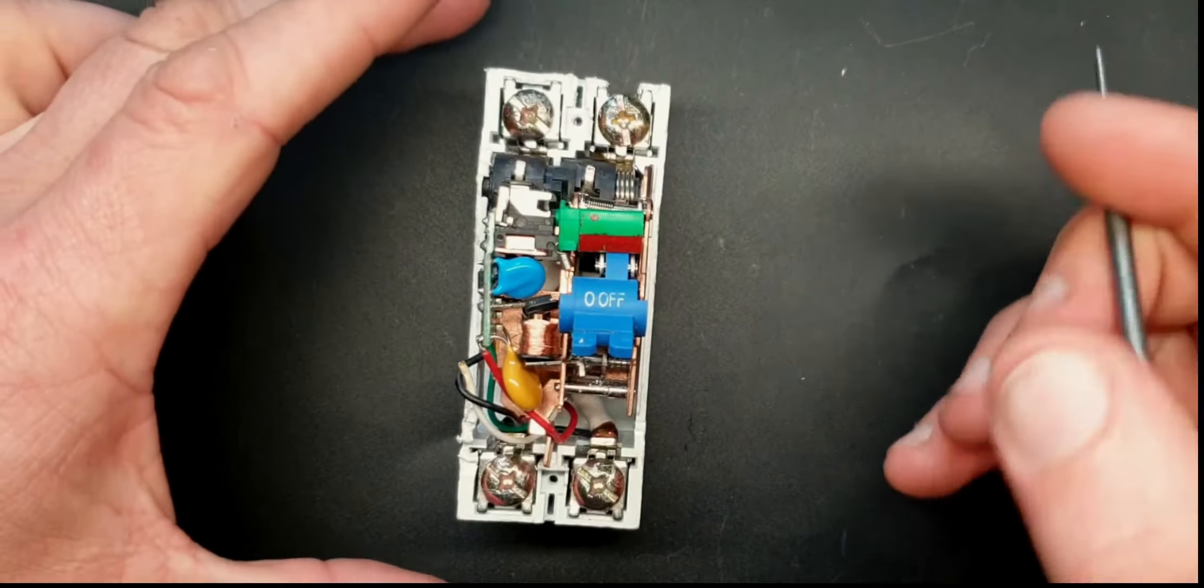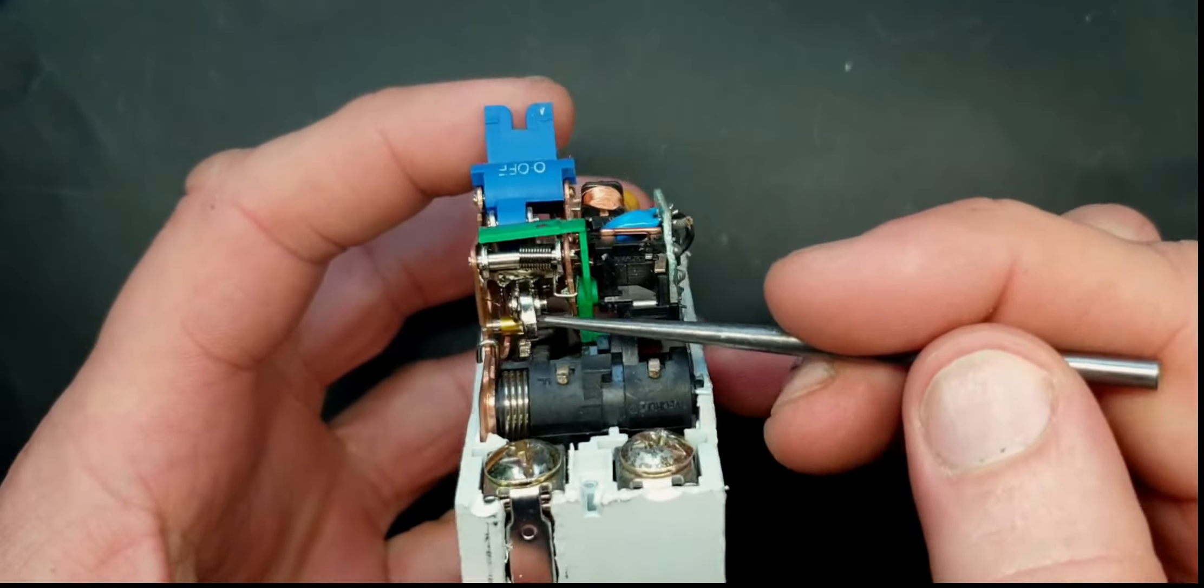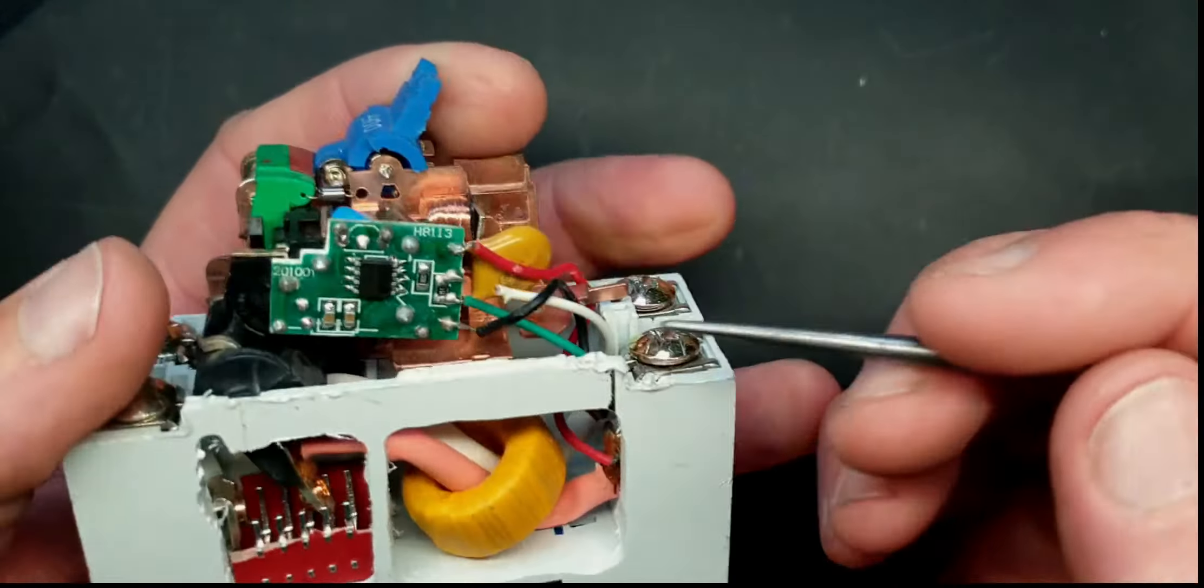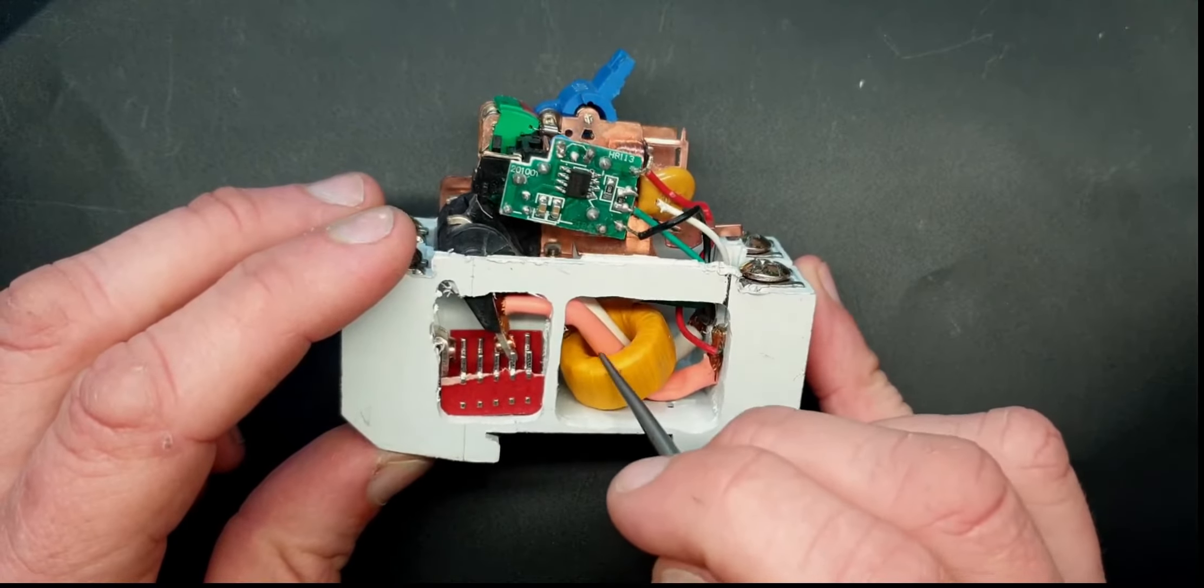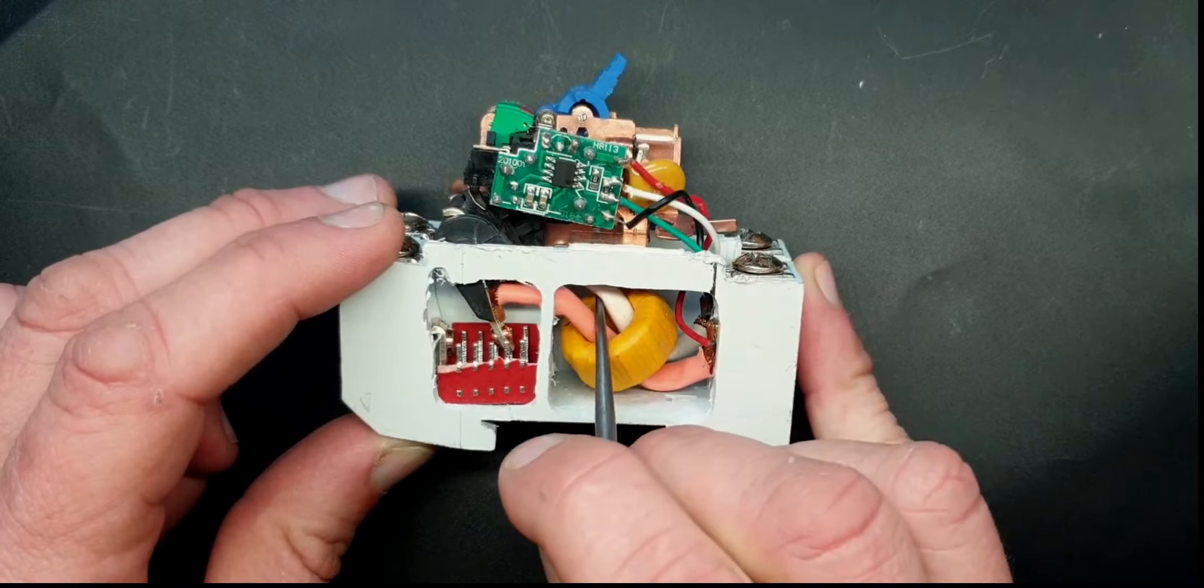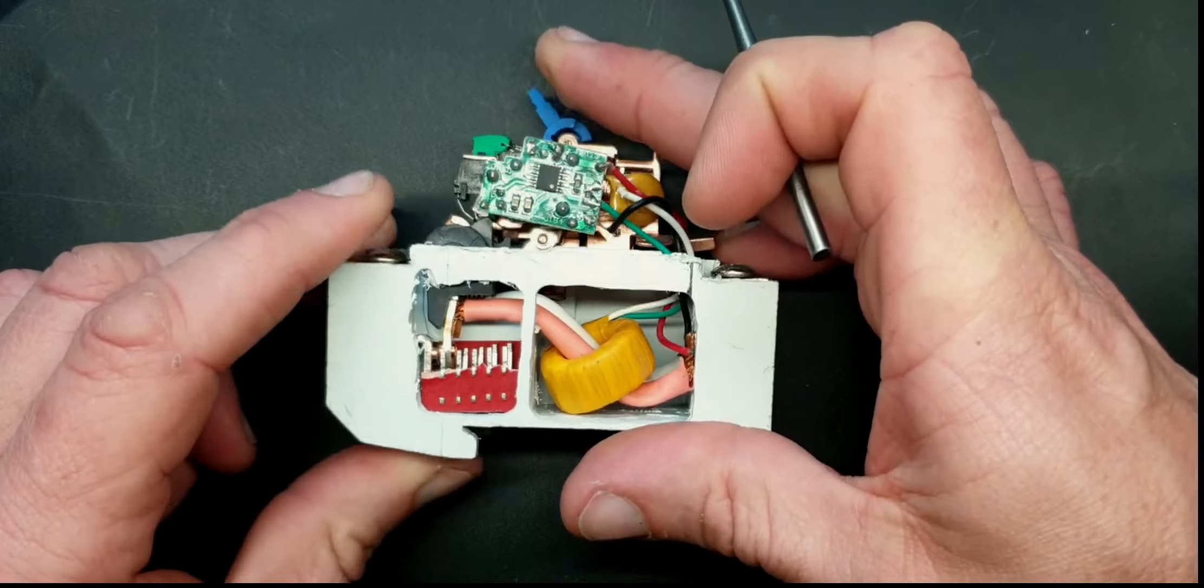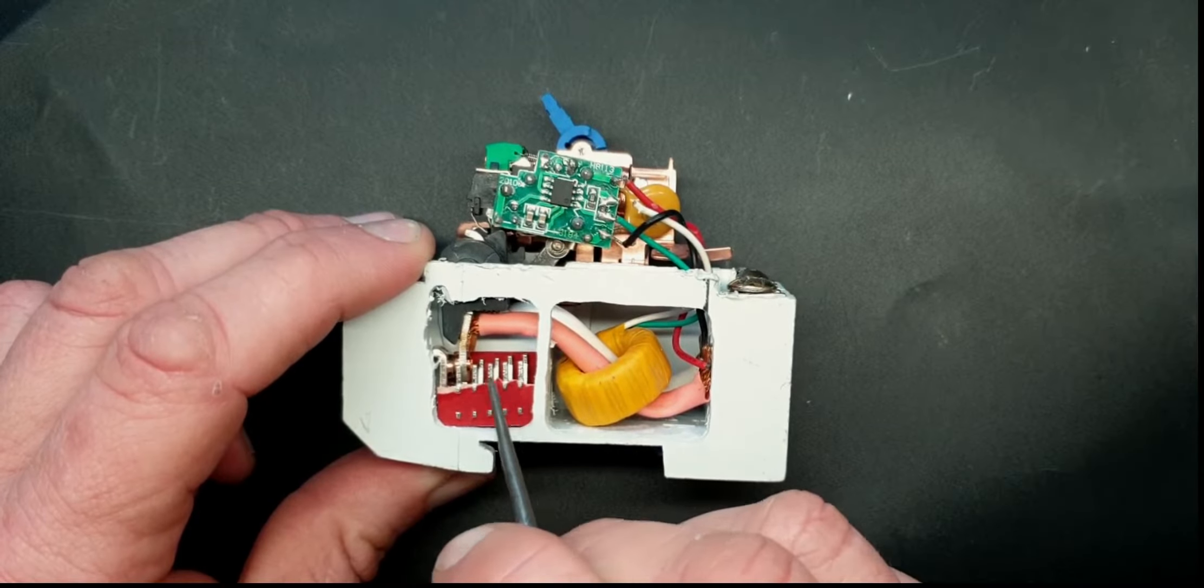A fair bit of stuff goes on in one of these. In here you've got your switch mechanism, your mousetrap mechanism, a bit of electronics here. You've got your incoming line, you've got your neutral at the back there, and this is your toroidal transformer.